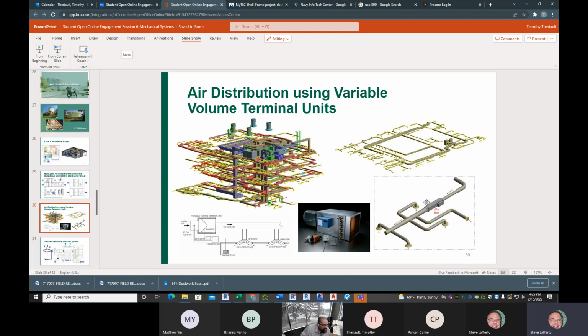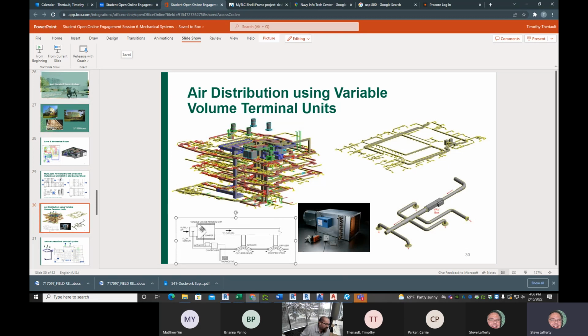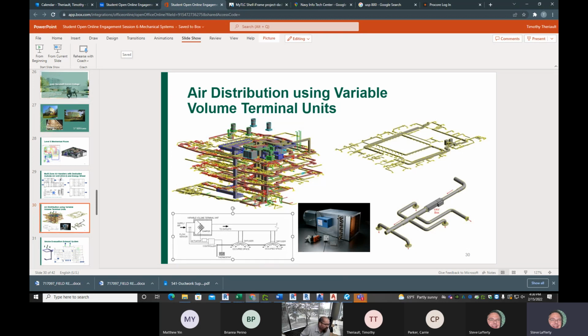So it's delivered through what's called a variable air volume box, or a variable terminal unit, it's also called. It delivers through this, being blown from the air handler, blown down, delivers through the box. The box modulates up and down. It has a damper inside of it that opens and closes, takes the higher pressure air from the air handler, and makes it a little bit lower pressure, which you would normally get on a single zone system, and delivers through diffusers down to the space, down to the people that are below it. This box is connected to a thermostat that's hanging on the wall.